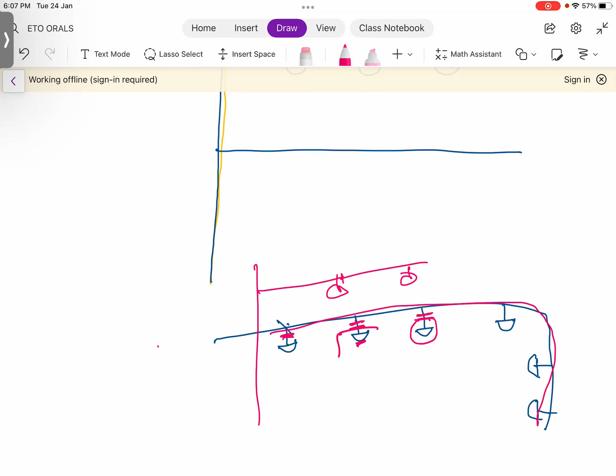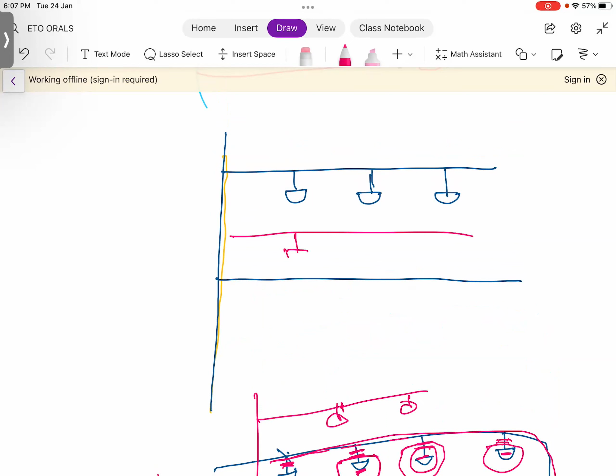We were using isolator at each detector. Every detector will have a short circuit isolator. Suppose there is a short circuit in this one, in this detector, right? It will phase it out. इसको remove कर देगा. Your other section is working well and good. Suppose यहाँ पे short circuit हुआ, ये वाला separate हो जाएगा, right? Means इसको वो isolate कर देगा. Separate out means isolate, right? Suppose here is one isolator. There is fault in this. This will isolate because of the isolator.